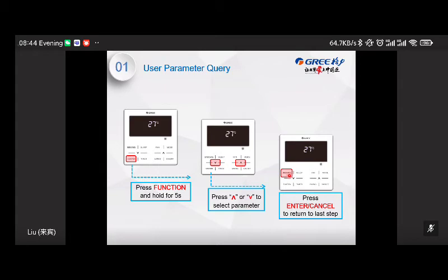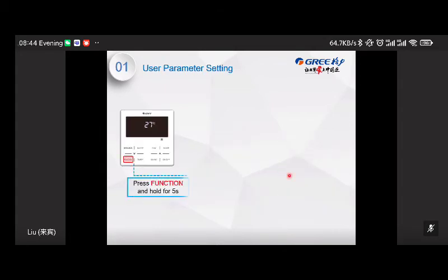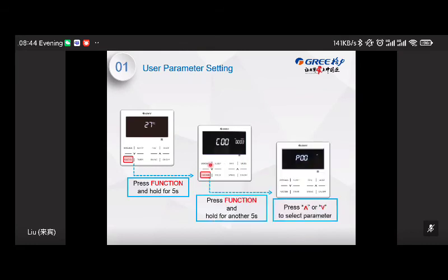This is the user parameter checking. For the user parameter setting, the operation is very similar. Press function button for 5 seconds. Then press this function and hold for another 5 seconds, and then you can see the code display here is changed from C to P. I think P stands for program. That means now you can change the setting of the VRF in this menu. Use up and down button to change the parameter.